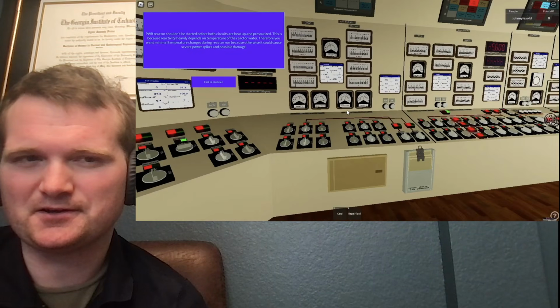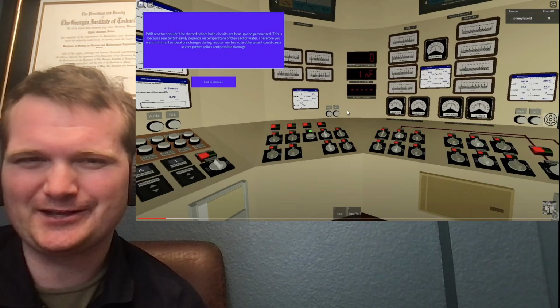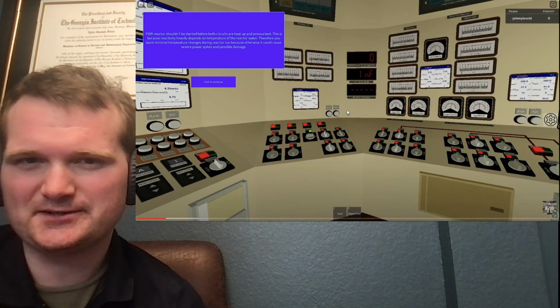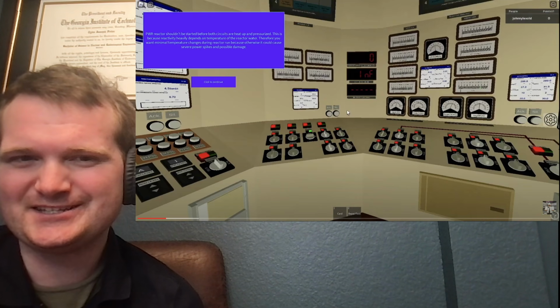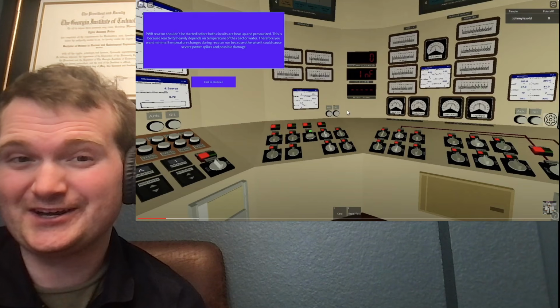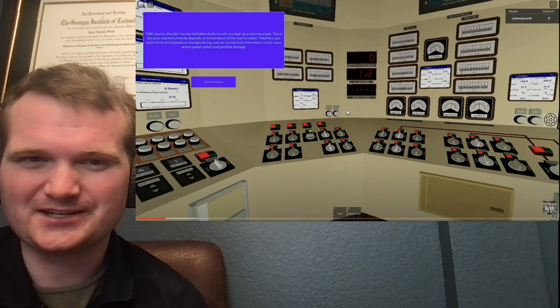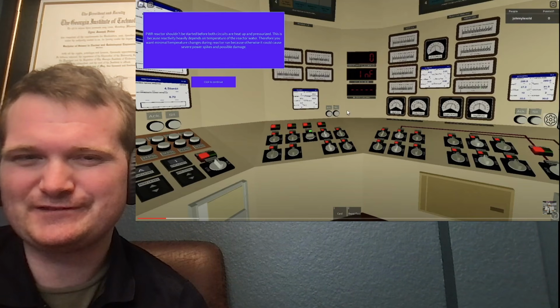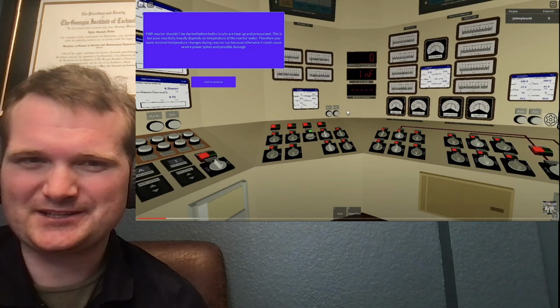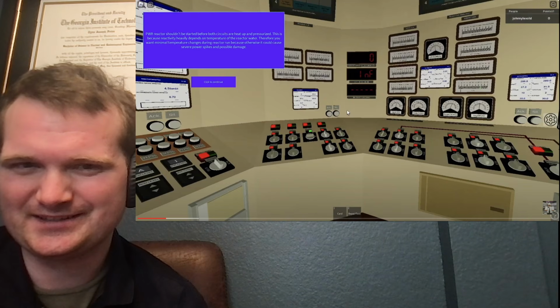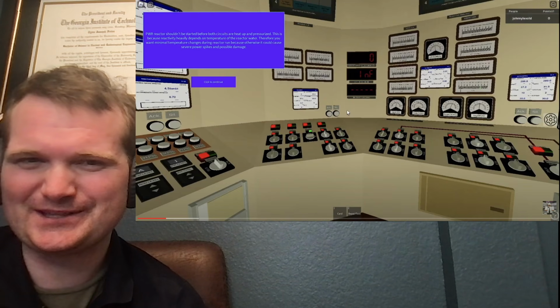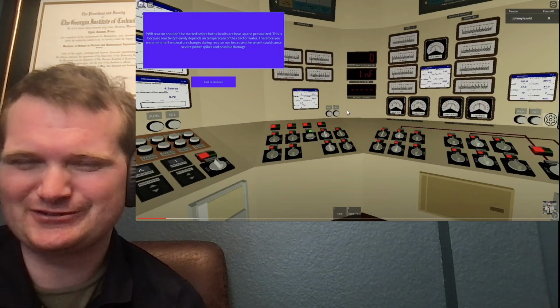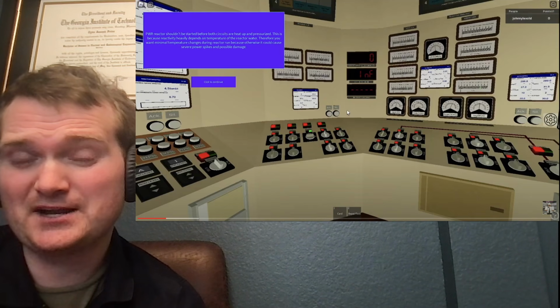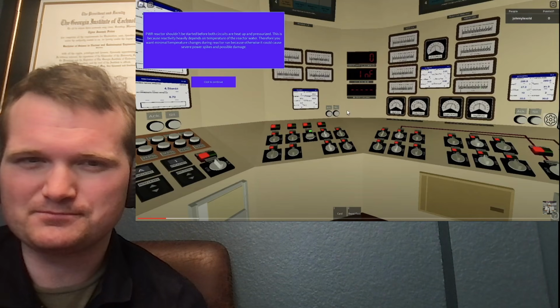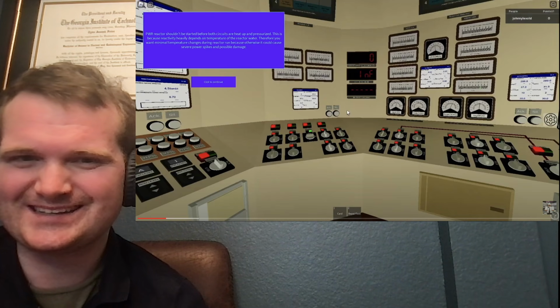Pressurizer starter heater. That's not a real thing, at least not at the plant that I worked at. You have an array of pressurizer heaters, but this is for gameplay purposes to make your heat up rate go way up so the game would be more interesting. When you're doing a real plant heat up, you're restricted to 50 degrees Fahrenheit per hour. Basically, you're going from 100 degrees Fahrenheit all the way up to 567 degrees Fahrenheit. So not really the most riveting gameplay experience. So I can understand why that's in there. But you would energize heaters, just not a really big one. That would be multiple megawatts of heat.